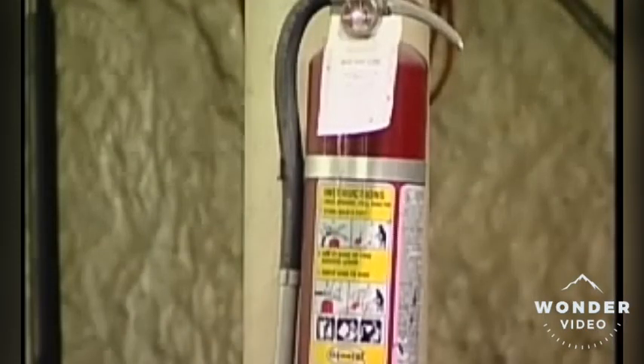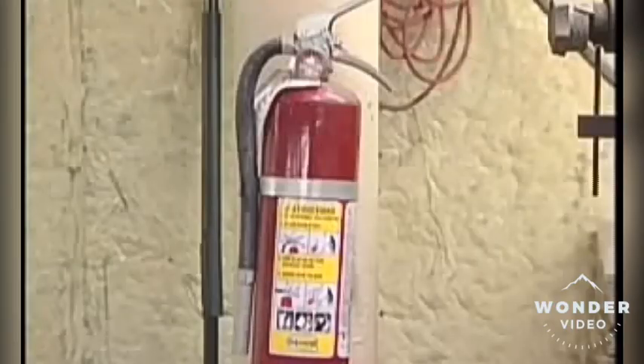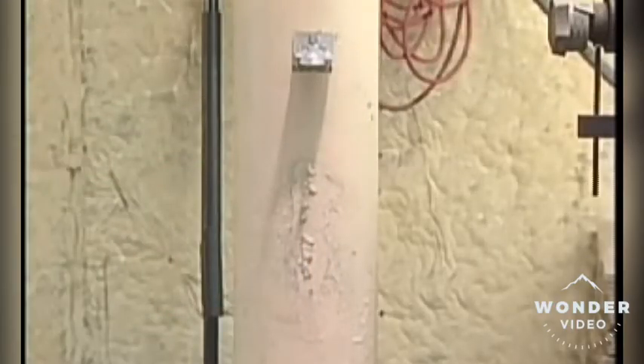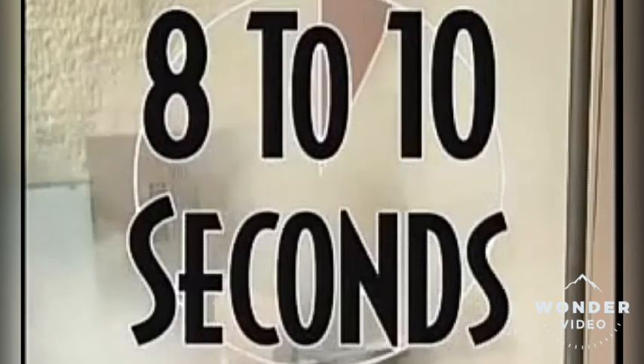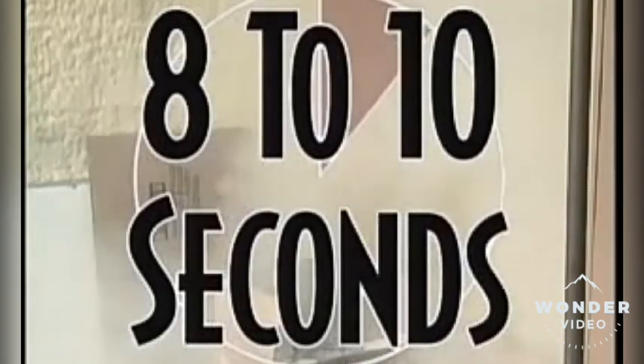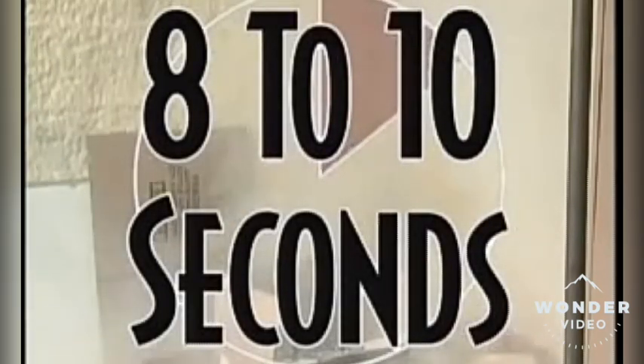Choose an extinguisher that is easy to reach and in working order, that is, it is fully charged. Also make sure the extinguisher is large enough to put out the fire within 8 to 10 seconds. That's how long you'll have, because most extinguishers completely discharge their extinguishing agent in under 10 seconds.